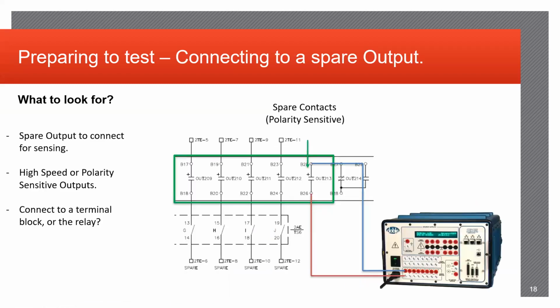So connecting spare output, this is a common practice for testing because it's extremely easy to manipulate a spare output that's not going to be utilized. Usually, again, by doing this, you'll connect directly to the back of the relay, because if it's a spare output, it won't have anything connected to it to begin with. The spare output contact is used for manipulating elements, testing them, and verifying them.